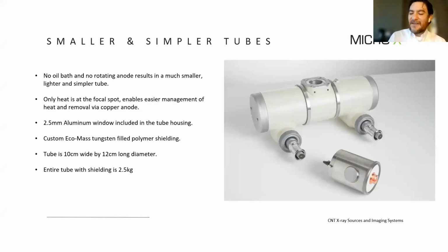Because we don't have an oil bath, we're able to bring the X-ray shielding much closer to the tube. We use EcoMass, which is a tungsten-filled polymer, around the tube to make a smaller shielding. And we incorporate an aluminum window directly on the tube. So all of these things together allow us to make a very small, very lightweight, very high power X-ray tube.